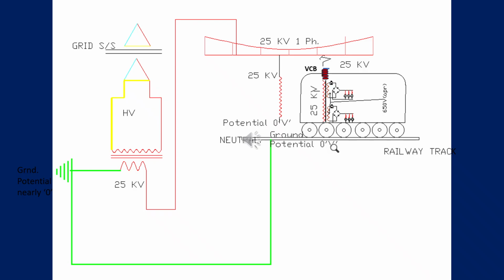Then you know our control circuit is working with 110 volt DC, but we cannot work directly on this power circuit, that means this 650 volt and everything. So what are we using? We are using electromagnetic relays or electro-pneumatic contactors, so that we cannot directly contact the power circuit in live condition.